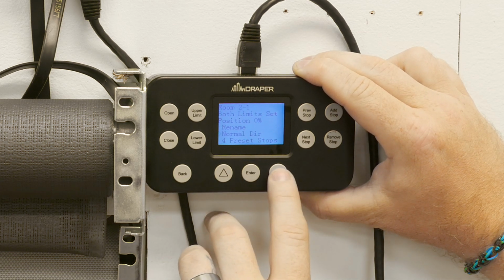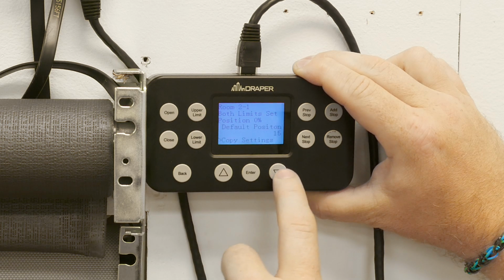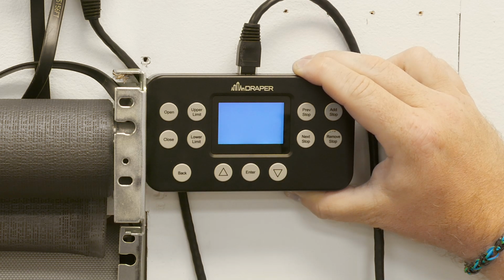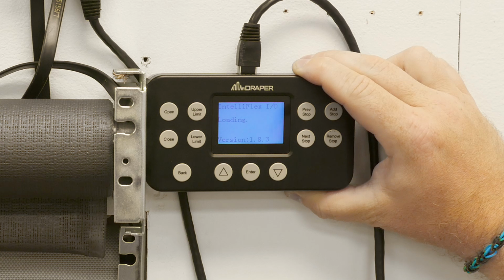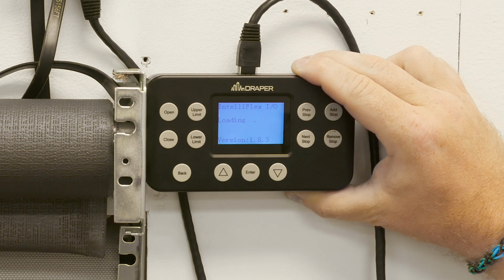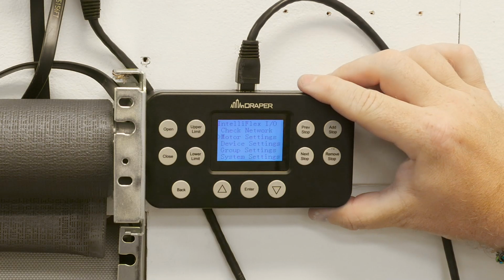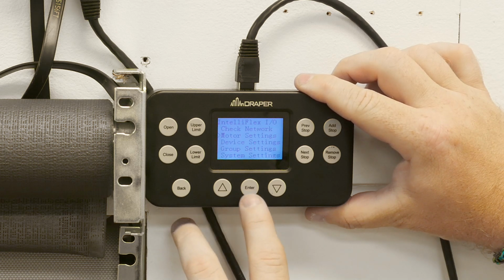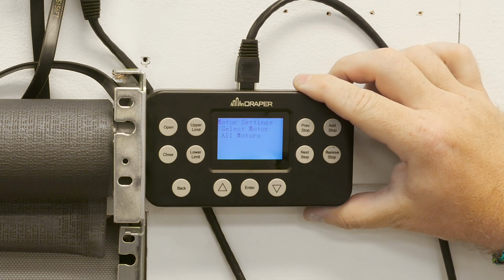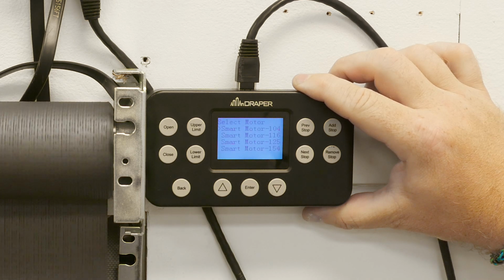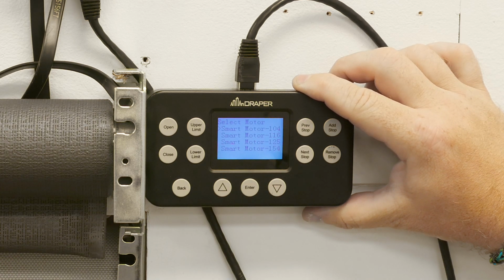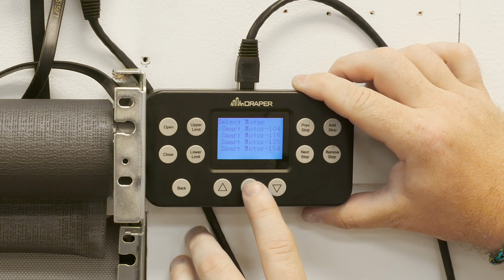As I can see, both of my limits are set, so I'm going to go ahead and reset this motor so we can do a limit setting procedure directly from the NDC. So I've reset the motor, it's going to load. Now that my motor is reset, I'm going to navigate back down to motor settings and hit enter. I'm going to select motor. Okay, my motor is jogging up and down. That is the one I want to configure, so I'm going to hit enter again.